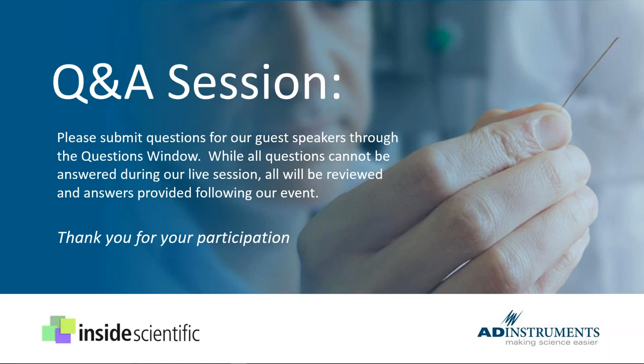Okay, perfect. How about your experience with the addition of heparin to a blood solution when you're doing a cuvette calibration? Is this a suggested best practice? And if people are using heparin, should they expect that this changes their calibration, so to speak? Does that have any effect on blood resistivity and the resulting cuvette cal that comes out?